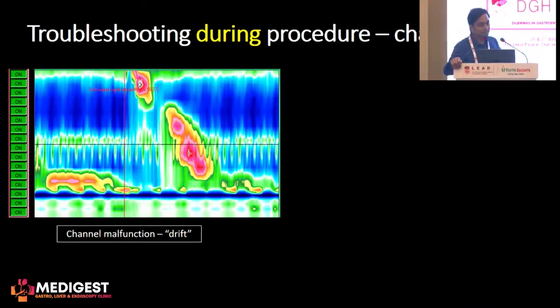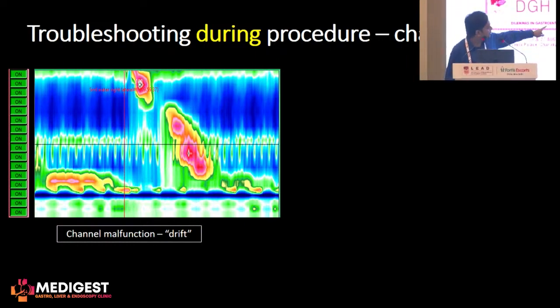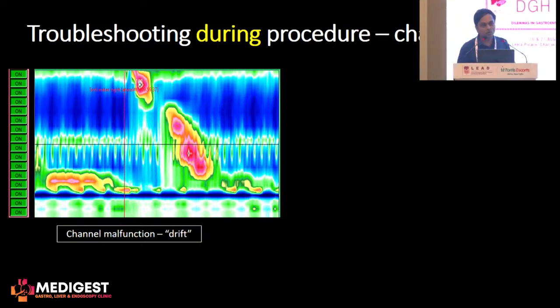Another thing that can happen is that during the procedure you suddenly see that one of the channels is showing an abnormal pressure — for example, a dark blue line at the bottom — meaning that specific channel is not working correctly.